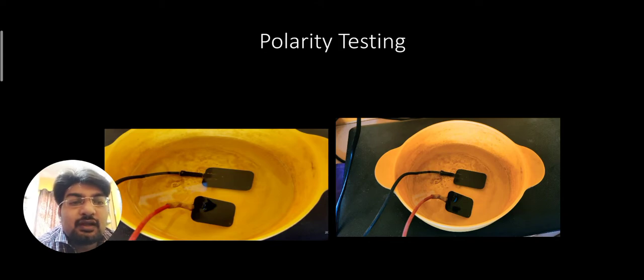What is the anode? It is a positive electrode with the lowest concentration of electrons, and the cathode is a negative electrode with the greatest concentration of electrons. The polarity switch designates one electrode as positive and one as negative. With AC current and interrupted direct current, polarity is not critical. Selecting negative polarity for muscle contraction facilitates membrane depolarization and is usually considered more comfortable. The negative electrode is usually positioned distally.